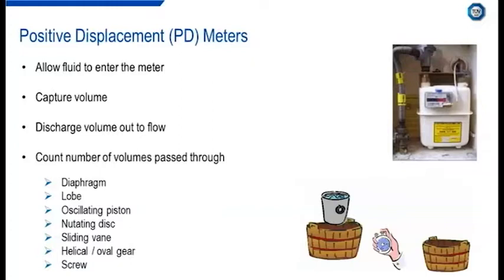Positive displacement meters, another common type of single-phase metering technology, operate by allowing the fluid to flow through the meter, capturing a volume briefly before discharging, and then counting the amount of volumes that have passed through the meter to get the flow output. In this respect, a bucket lifting water out of a pool, counting the number of times that we carry out that operation, timing the operation, and knowing the volume of the bucket is a simple positive displacement meter. There are a few examples of PD meters listed on the screen. The diaphragm meter is our typical domestic gas meter, and the oscillating piston meter is commonly used for domestic water metering.